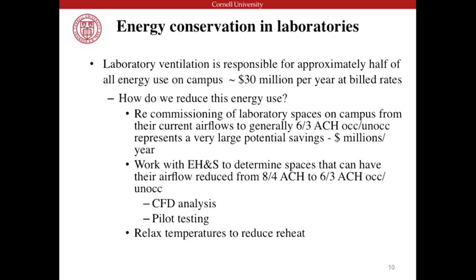We talked a little about recommissioning lab spaces. What we started looking at was whether we were over-ventilating the spaces. We worked hand in hand with EH&S to see if we could reduce the ventilation rate from typically 8 air changes occupied and 4 air changes unoccupied, down to 6 air changes occupied and 3 air changes unoccupied. That could mean possibly millions of dollars in savings, so we decided to take a look at it.